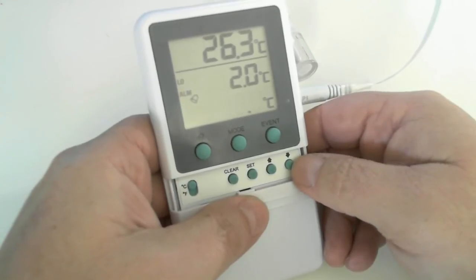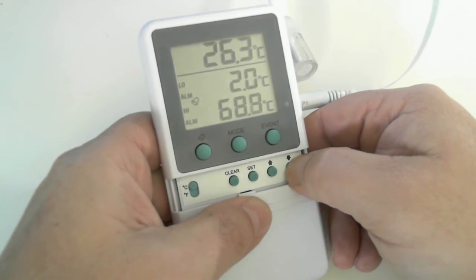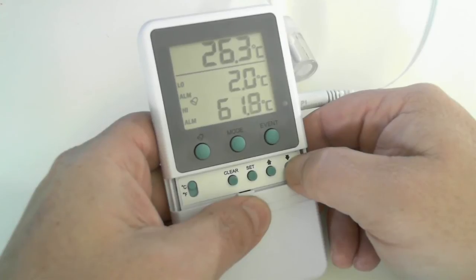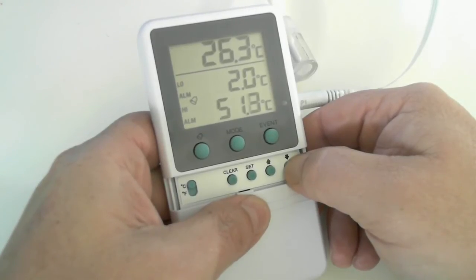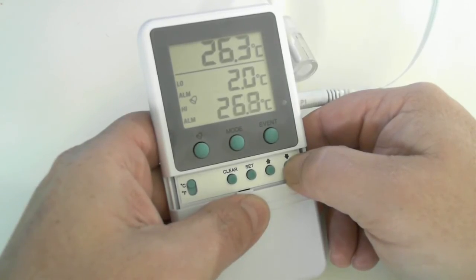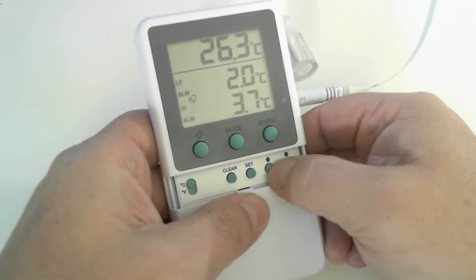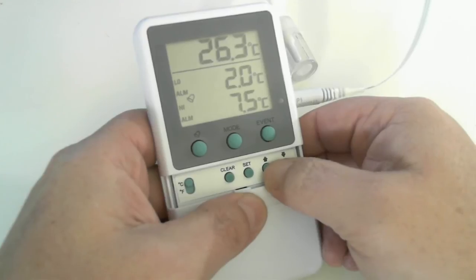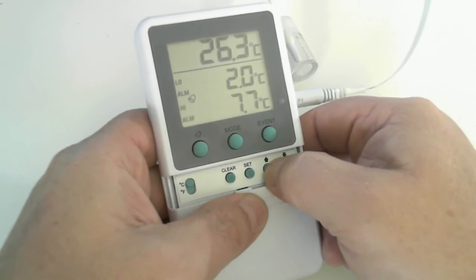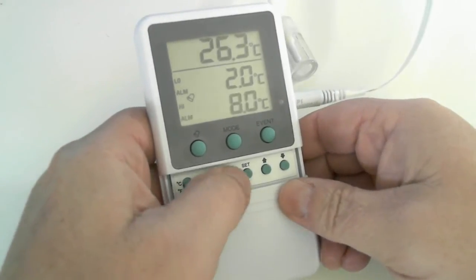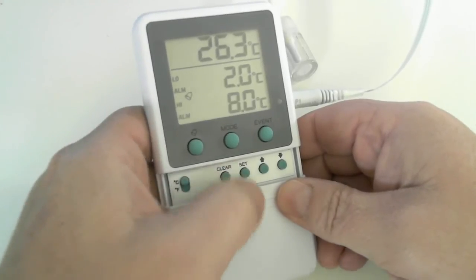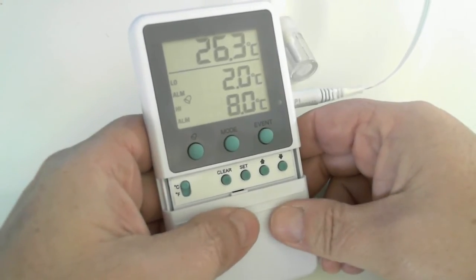And I'll set our high for 8 degrees C. Now, when we do set our high alarm for 8 degrees C, that is lower than 26.3 degrees C, which is our current room temperature measured by the bottle thermometer. Went a little too far there. Let's go back up. And as I said, once I hit that set, we will go into an alarm condition. But that's okay.